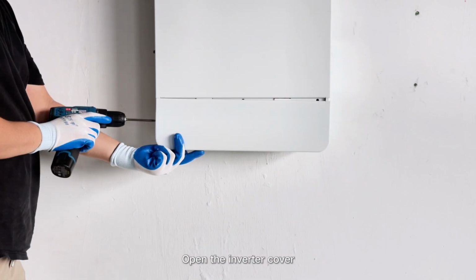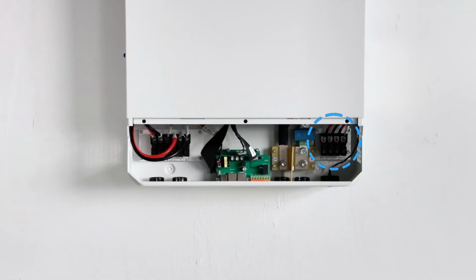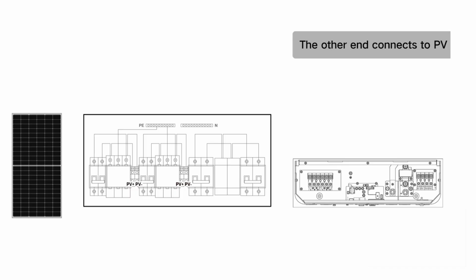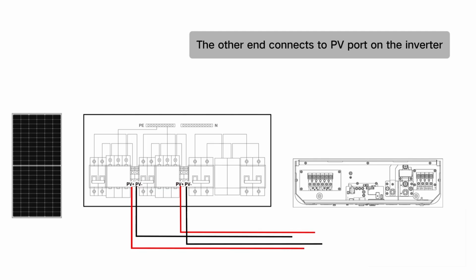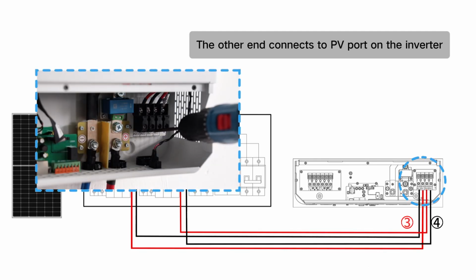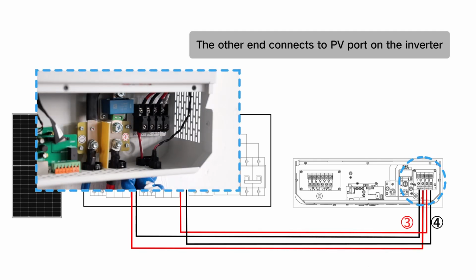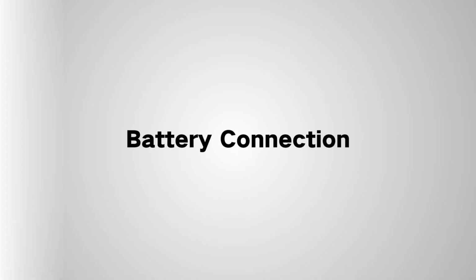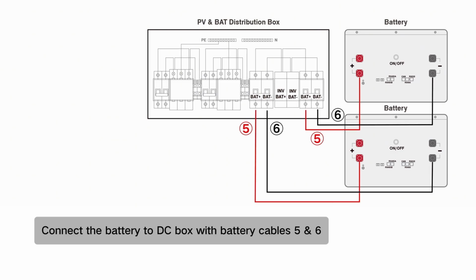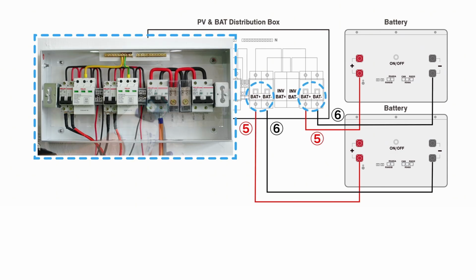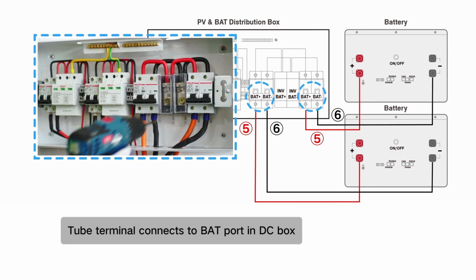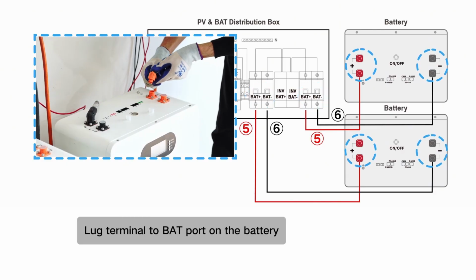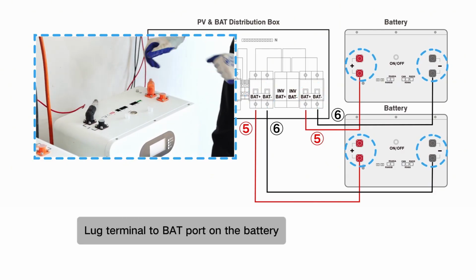Open the inverter cover. The other end connects to the PV port on the inverter. Battery connection. Connect the battery to the DC box with battery cables 5 and 6. Tube terminal connects to the BAT port in the DC box. Lug terminal to the BAT port on the battery.